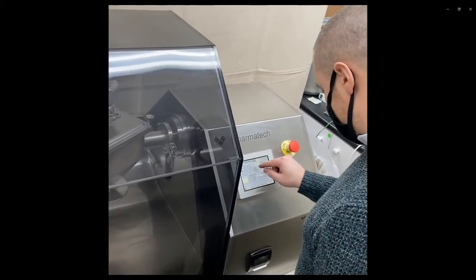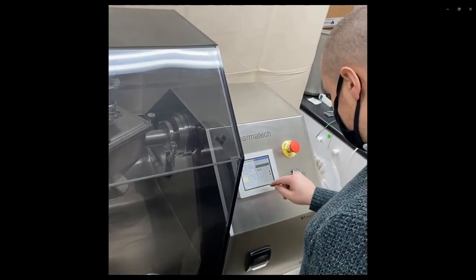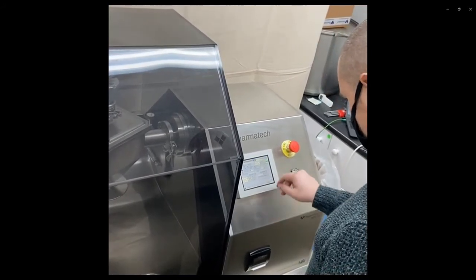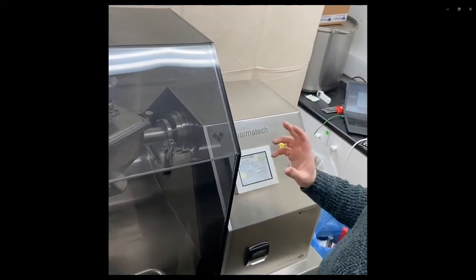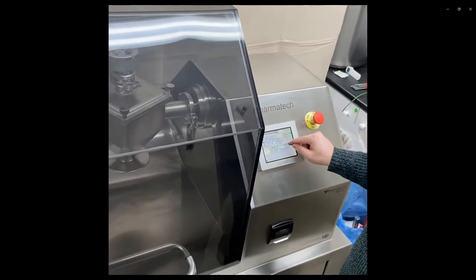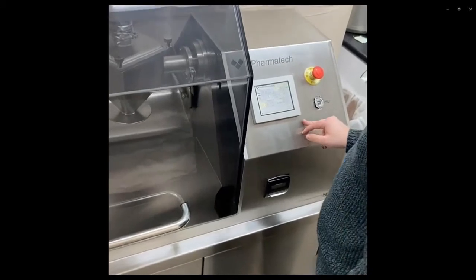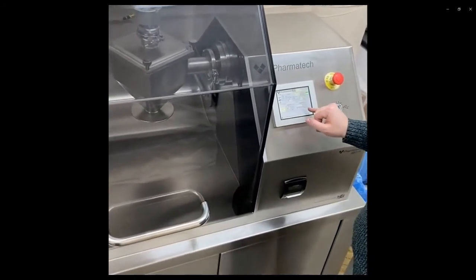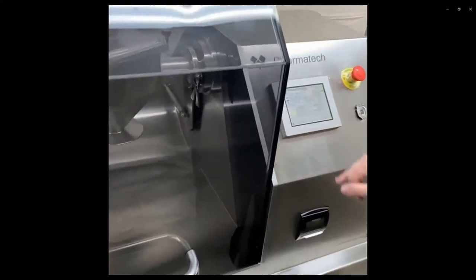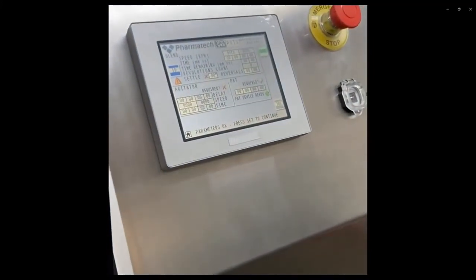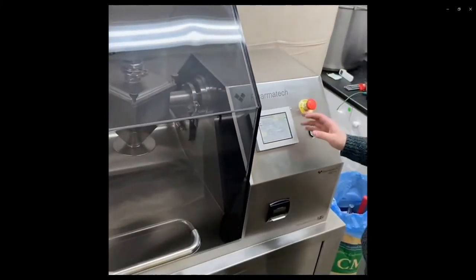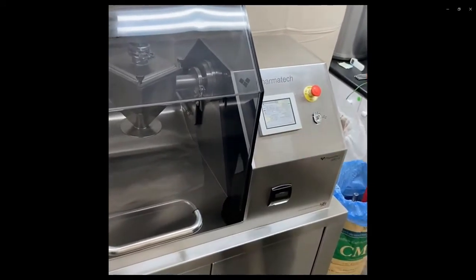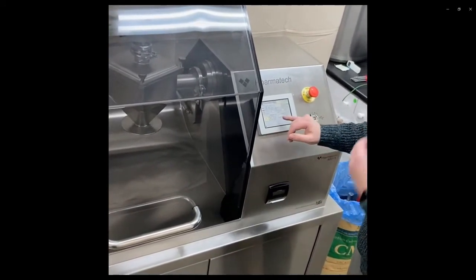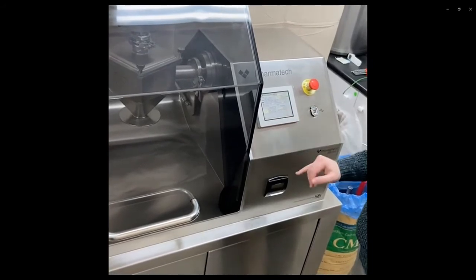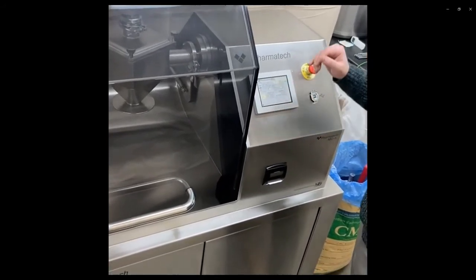Entering the speed blend parameter in RPM, time in minutes, and then because we've got the PAT device, you have to activate the handshake, and we can already see that the OPC server is working because we've got a PAT device ready. And in some instances you may want to ignore the first 2, 5, 10 minutes of a blend before you want to start capturing data, in which case you have a trigger delay for the PAT device, which can be set from the blender HMI.